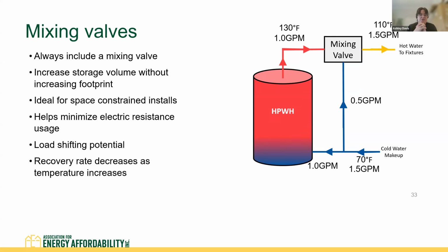It's important to not set your mixing or your set point temperature of your heat pump water heater too high. A lot of these tank type heat pump water heaters go up to about 140 degrees, but they do start to lose capacity. They start to lose efficiency at those really high temperatures. And then you can't load shift any further if you're already at the max temperature. So choosing a temperature that's higher than you want it to be delivered, but not so high that you're compromising efficiency is going to help you really maximize the storage there. Next slide.